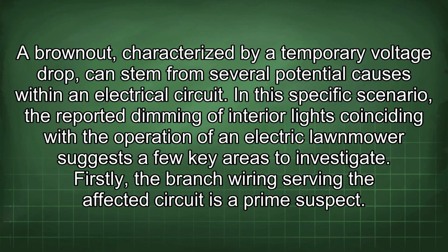A brownout, characterized by a temporary voltage drop, can stem from several potential causes within an electrical circuit. In this specific scenario, the reported dimming of interior lights coinciding with the operation of an electric lawnmower suggests a few key areas to investigate. Firstly, the branch wiring serving the affected circuit is a prime suspect.